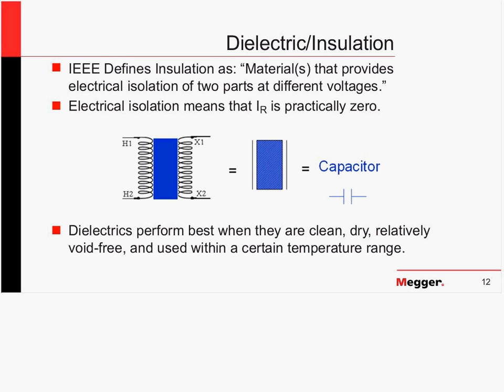This is because there are polarization effects, physical effects happening in the materials when they're subjected to a field. So we're going to talk about polarization losses in a few minutes and their contribution to losses, because I sub R component is what feeds the losses that we measure when we do power factor measurements.